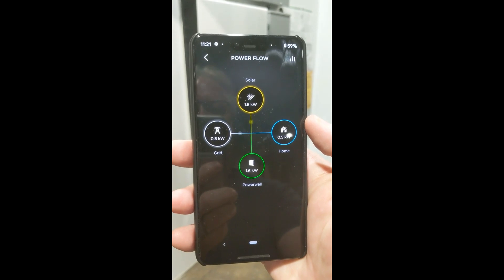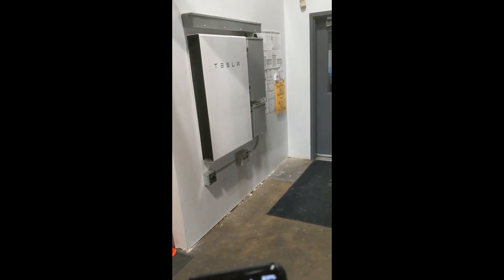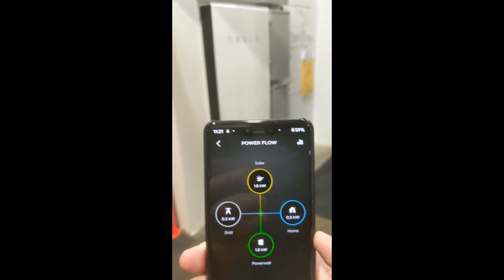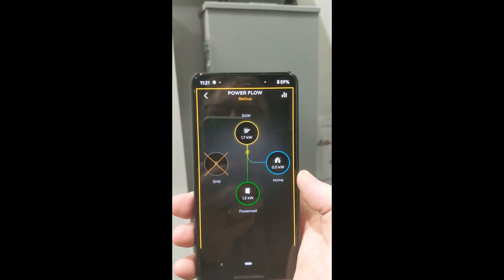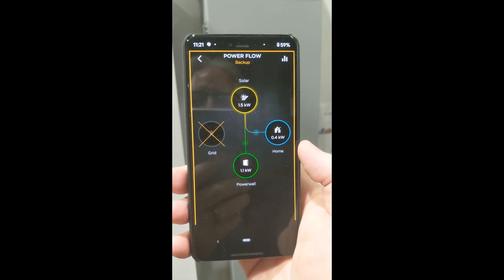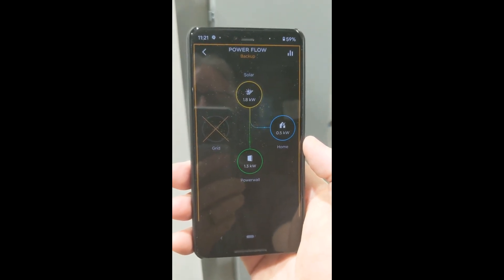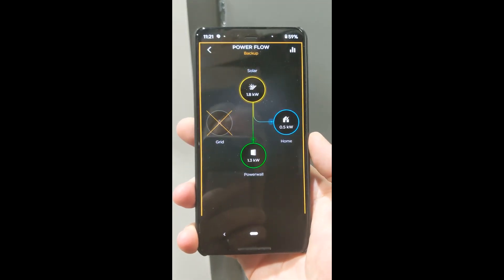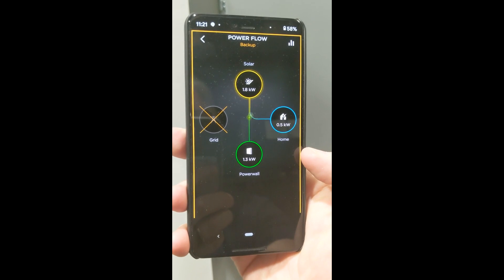I'm going to ask somebody to go ahead and kill the power for this part of the building. There's a little bit of a delay. When it detects a power failure, the backup gateway automatically disconnects from the grid because it sees it's having problems, and continues to keep solar working. You can see we're generating more than we're using and using the excess to charge the battery. We could go all day like this, probably have the battery fully charged within a couple hours, then continue to run from solar, and in the evening when the sun went down we'd run only from the battery.